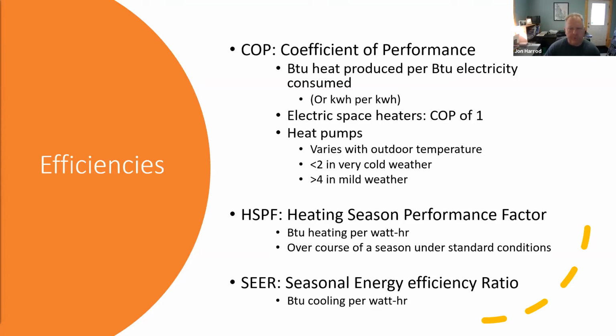Electric space heaters produce one BTU of heat for each BTU of electricity you put into it. So they're essentially 100% efficient at turning electricity into heat. But heat pumps, through this refrigeration cycle, are able to achieve much higher coefficients of performance. How efficient they are is going to vary with the outdoor temperature. The colder it is, the harder they have to work to extract that heat. But heat pumps are typically able to extract anywhere between 2 and sometimes more than 4 units of heat energy for each unit of electrical energy that you put in. So they're 200 to 400+% efficient.